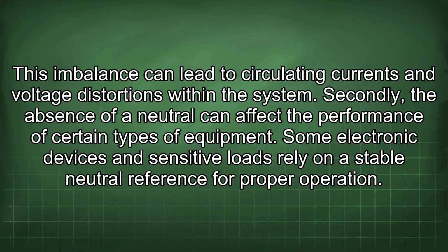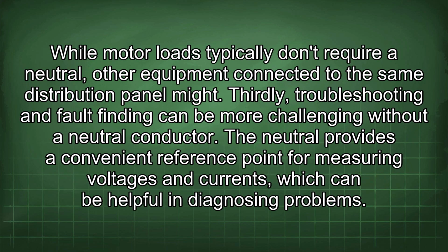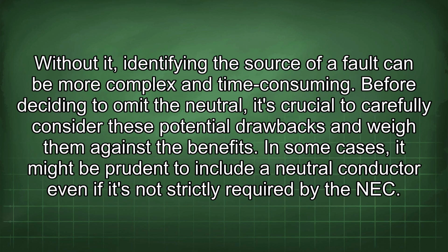Secondly, the absence of a neutral can affect the performance of certain types of equipment. Some electronic devices and sensitive loads rely on a stable neutral reference for proper operation. While motor loads typically don't require a neutral, other equipment connected to the same distribution panel might. Thirdly, troubleshooting and fault finding can be more challenging without a neutral conductor. The neutral provides a convenient reference point for measuring voltages and currents, which can be helpful in diagnosing problems. Without it, identifying the source of a fault can be more complex and time-consuming.